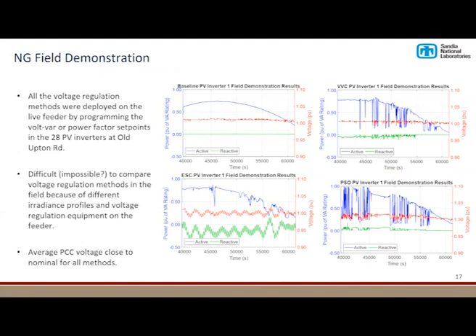And so here are the results for a baseline, the volt-var control or volt-var curve, extremum seeking control, and particle swarm optimization. It's essentially impossible to compare these, because there are going to be different set points for voltage regulation equipment on the feeder, and there are obviously different irradiance profiles. The PSO run had high variability, whereas the baseline was a nice clear day. It more or less just shows that in all cases, we're relatively close to nominal voltage, so the red lines here are close to unity.